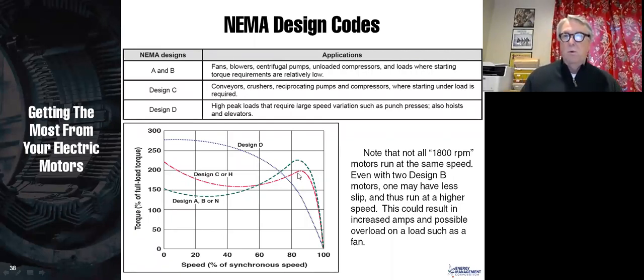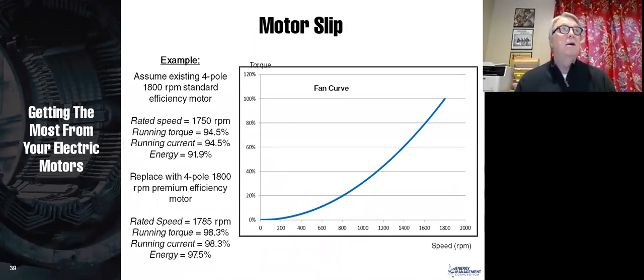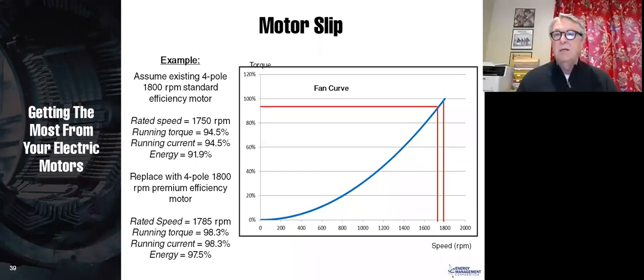Let me make a point here that I don't want to dwell on: the higher the efficiency of a motor, generally the lower the slip. So let's say you have a standard motor, and that standard motor runs at 1750 RPM. You decide to replace that with a high efficiency motor, which runs at 1785 RPM. Well, if we go over here, we can see that the standard motor was running at approximately 94% torque on a fan curve, and the high efficiency motor is running at 98%. Even though you put in a high efficiency motor, you're actually using more power than you were with the standard efficiency motor. Why is that? Because the slip is less, therefore the motor runs faster, and therefore it pumps more air.